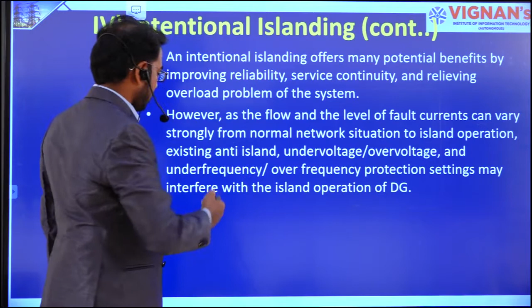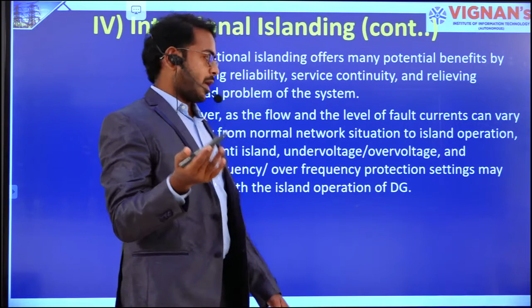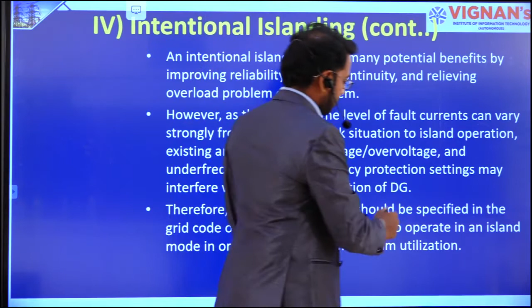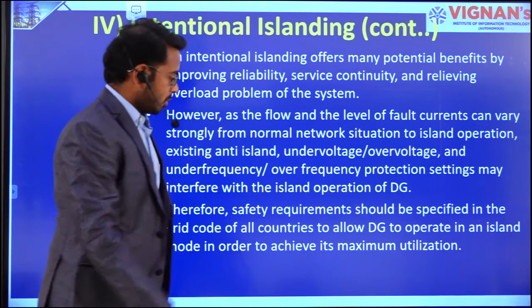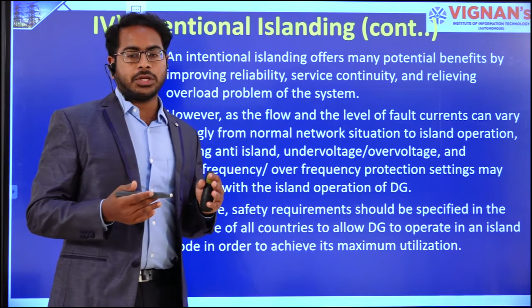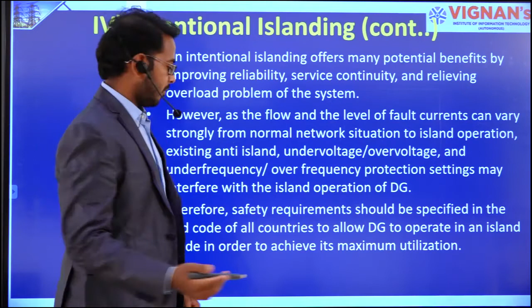However, the level of fault current can vary strongly from the normal network situation to the island operation. Existing anti-islanding or under voltage, over voltage, and under frequency, over frequency protection settings may interfere with the island operation of DG. We can put this protection equipment, as we already discussed: UV, OV, UF and OF protection settings to detect when an islanding condition is happening, to go for intentional islanding. Therefore, the safety requirements should be specified in a grid code. All countries allow DG to operate in island mode in order to achieve maximum utilization. So here also the grid code is supposed to give the range and the safety requirements for when a sudden islanding condition happens. For that, the grid code is supposed to give some guidelines.